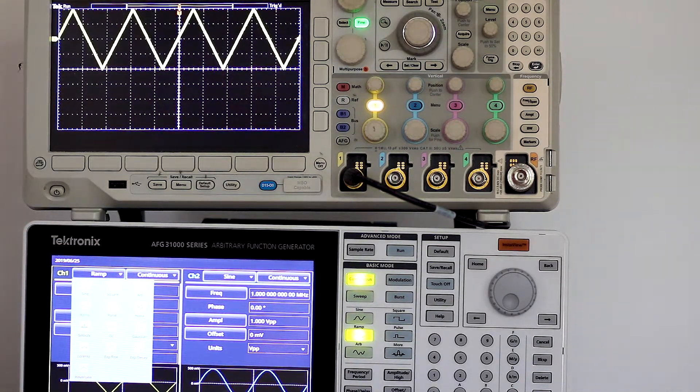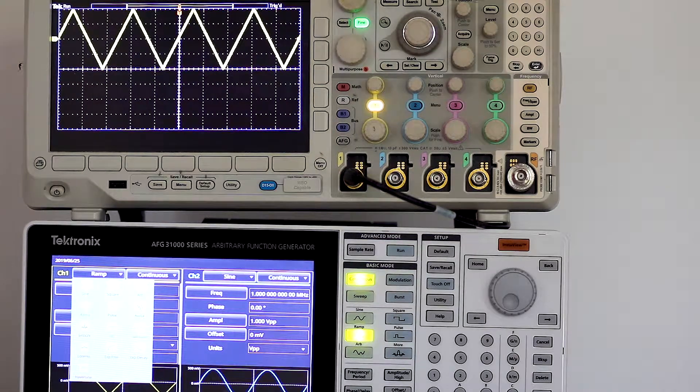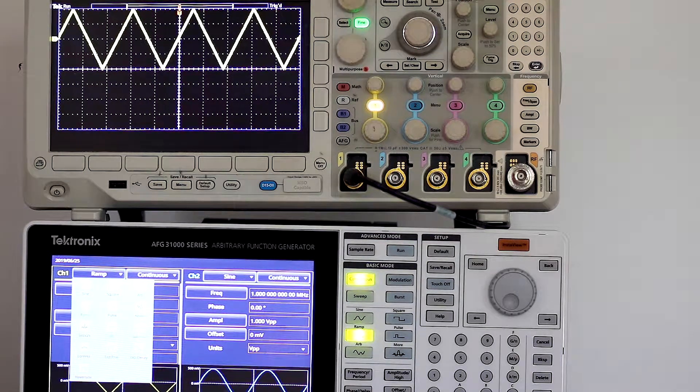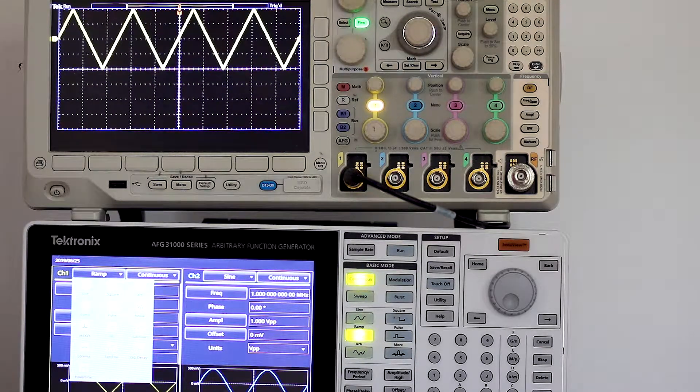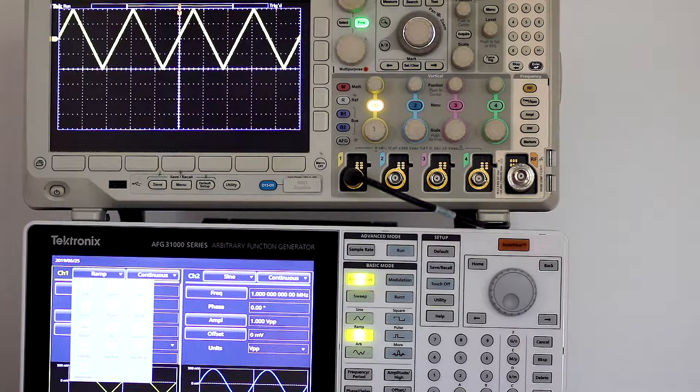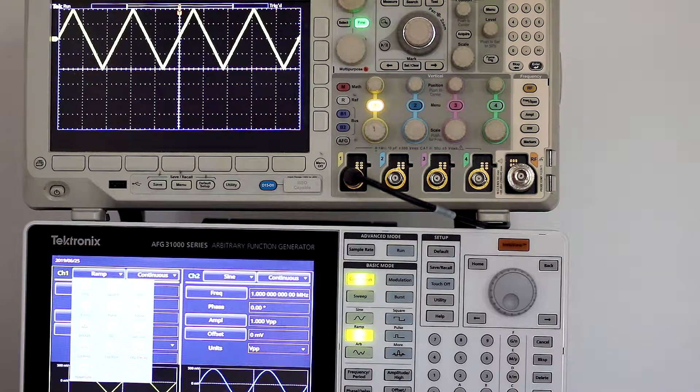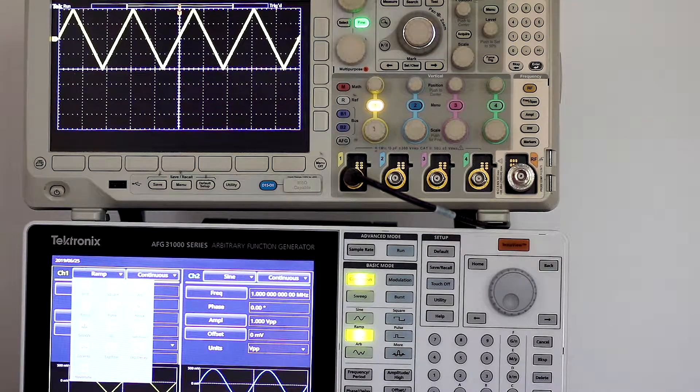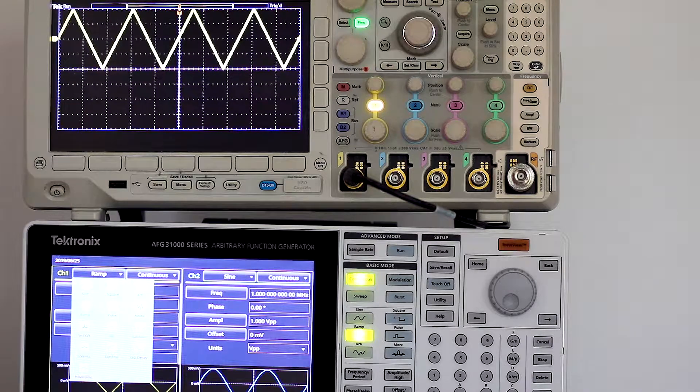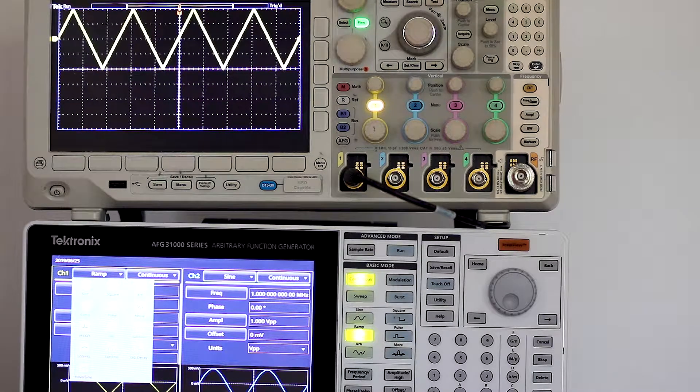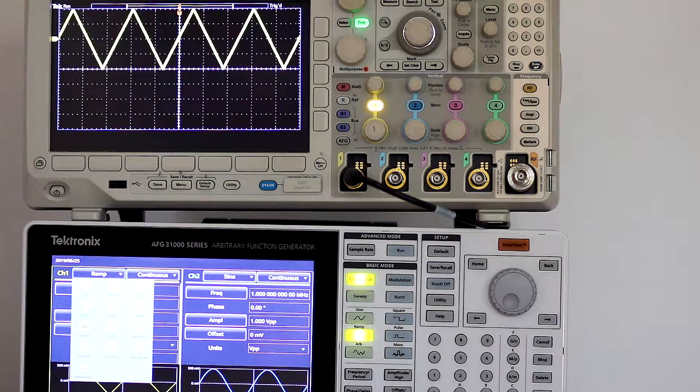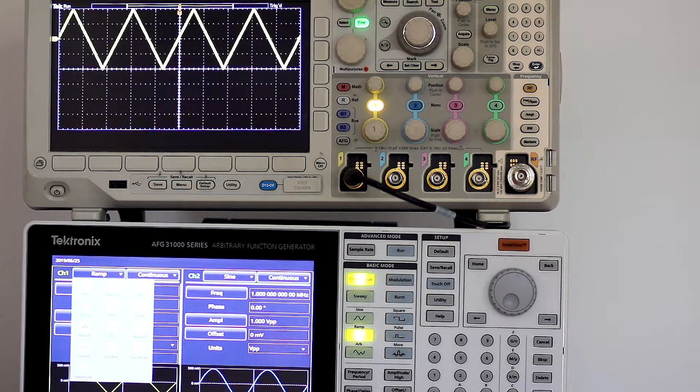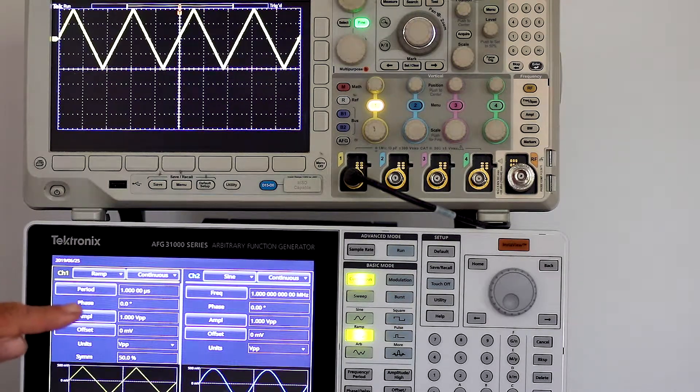In the continuous mode the AFG will send out any of the 12 waveforms in its reference library plus arbitrary, which permits the user to generate an almost infinite number of custom waveforms. When you first touch continuous, the default sine wave appears in both channels.